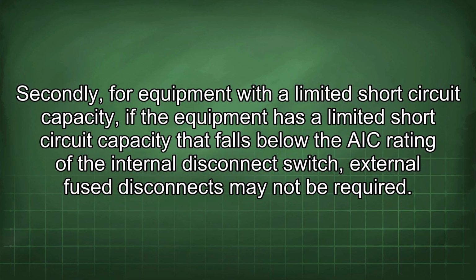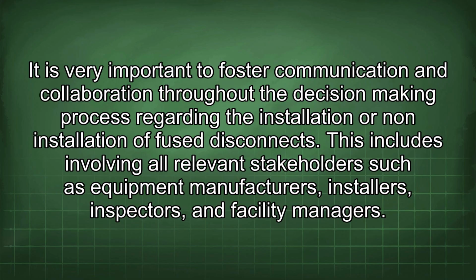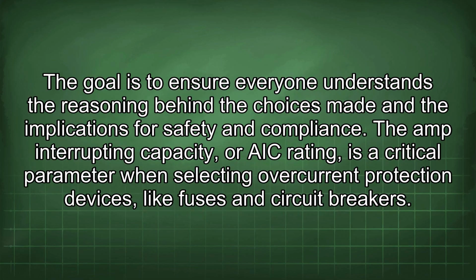Secondly, if the equipment has a limited short-circuit capacity that falls below the AIC rating of the internal disconnect switch, external fused disconnects may not be required. It is very important to foster communication and collaboration throughout the decision-making process regarding the installation or non-installation of fused disconnects. This includes involving all relevant stakeholders such as equipment manufacturers, installers, inspectors, and facility managers. The goal is to ensure everyone understands the reasoning behind the choices made and the implications for safety and compliance.